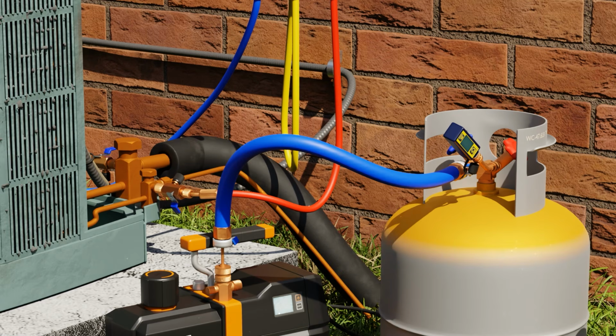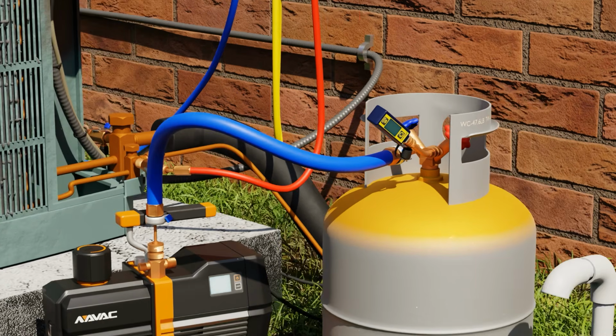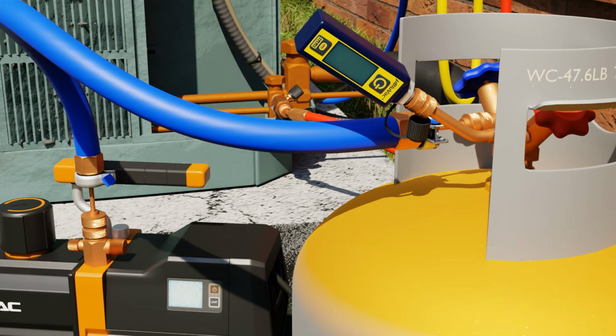You would then zero the scale and begin your recovery. If it had refrigerant in it beforehand, then you would need to take account of how much refrigerant was in it, and the whole point of this is to ensure that we don't overfill the tank beyond 80% full of liquid. You want to pull a vacuum below 500 microns on the tank. Here we show a vacuum pulled to 300 microns.